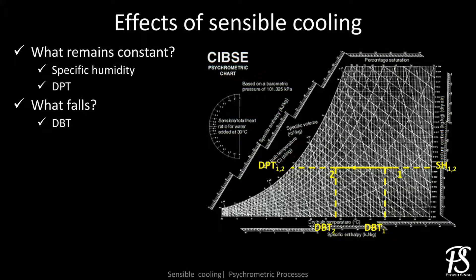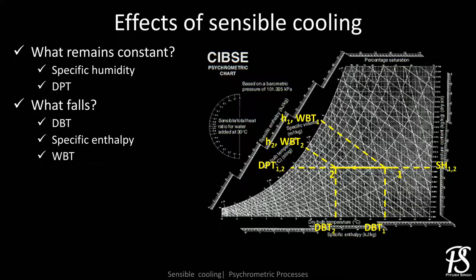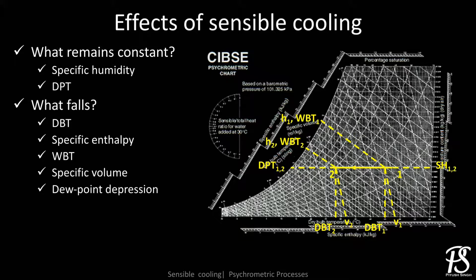The psychrometric properties that see a decrease in their value are: number one, dry bulb temperature — due to the removal of heat by the cooling coil, the temperature of air drops. Next is specific enthalpy — with the removal of heat by the cooling coil, the specific enthalpy of air drops. Wet bulb temperature also sees a drop in its value. The specific volume also decreases as the air becomes cooler. Since dew point temperature remains constant but dry bulb temperature drops, dew point depression also decreases. As the air moves closer to the saturation line, its moisture carrying capacity decreases, so we also observe a drop in wet bulb depression.